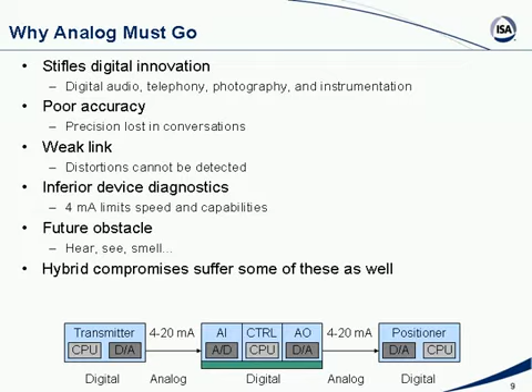Foundation Fieldbus also enables firmware download. So when new software becomes available for a Fieldbus device, you can actually download new firmware over the bus to that device, thereby upgrading it to take advantage of the latest diagnostics, etc. So you stave off obsolescence using Fieldbus. So yes, there are many reasons for going digital.